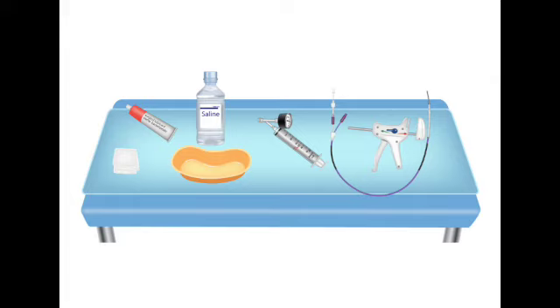Okay. First, you mount the syringe while the handle is in neutral. Then you switch the handle to the inflation position, and you pump it while the syringe is still dry, vigorously. This expels all the air that was initially trapped inside that syringe chamber. And once that air is out, you switch to deflation, you put the tip in sterile water, and you draw the fluid up precisely to the 35 cc marker.